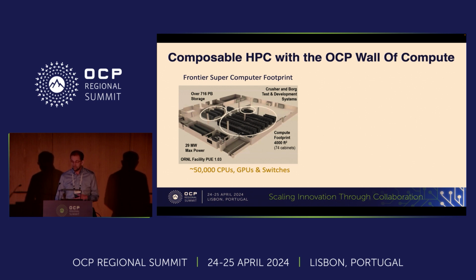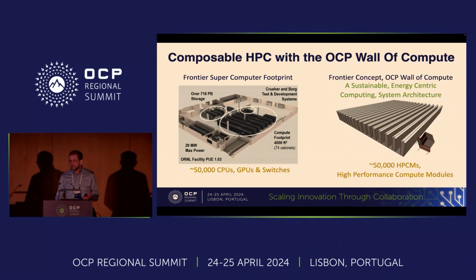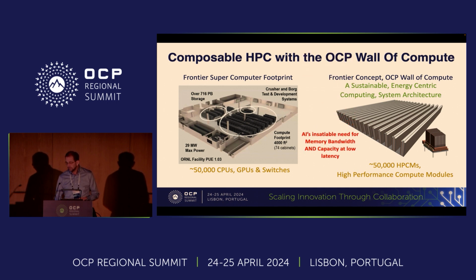And also there's the storage - the storage is actually separate to the actual main compute. In our implementation, we would have this wall of compute, with about 50,000 HPCMs, high-performance compute modules, where the modules could be CPUs, GPUs, or switches, just one amplified step away from the walls you see there. So that's a configuration where we've got rid of the 19-inch racks.